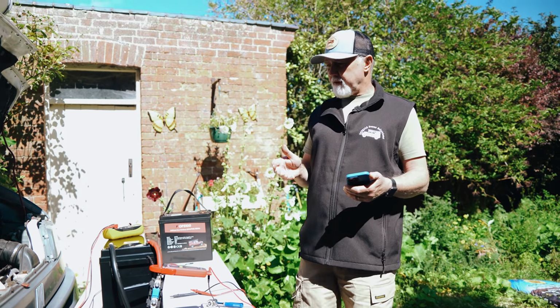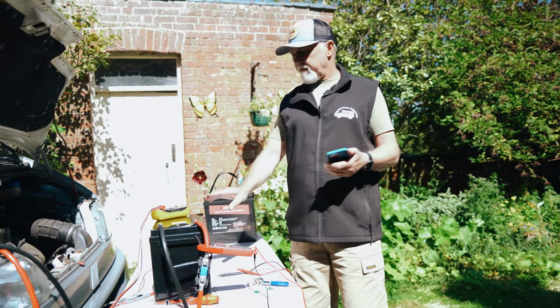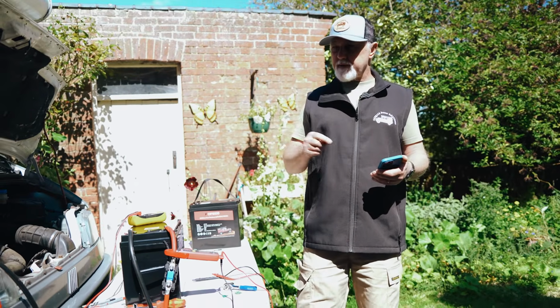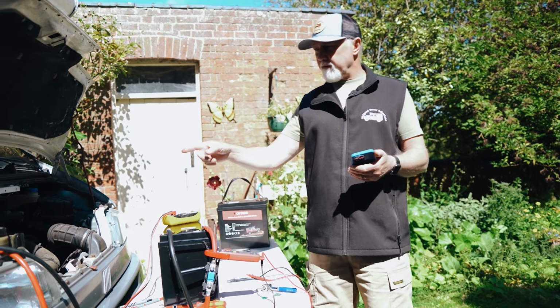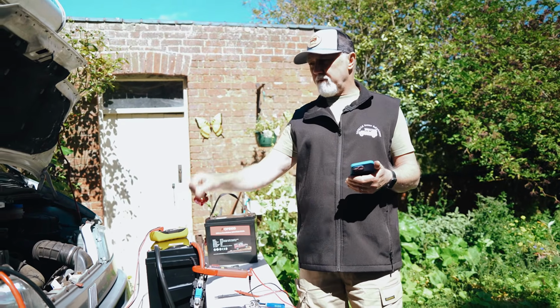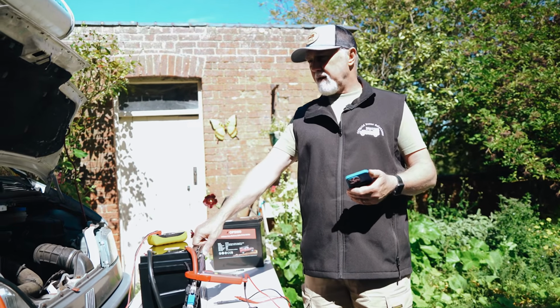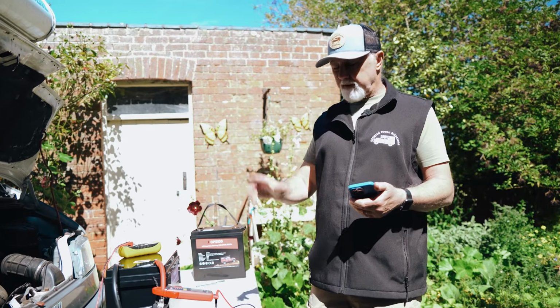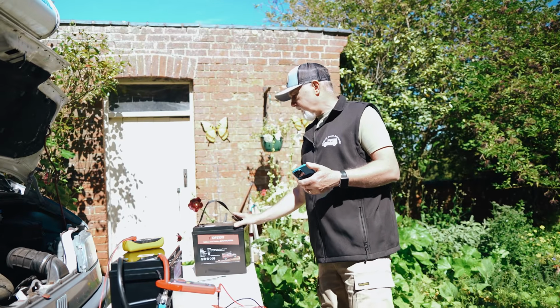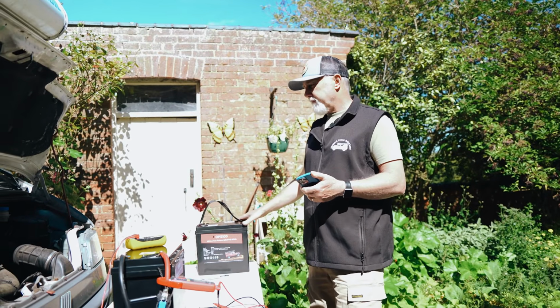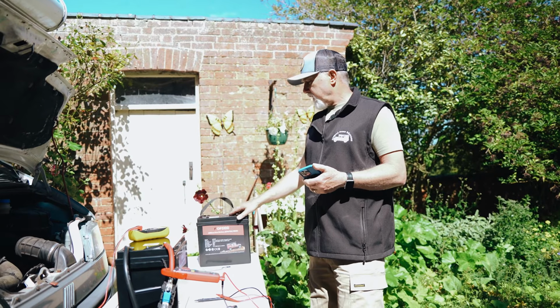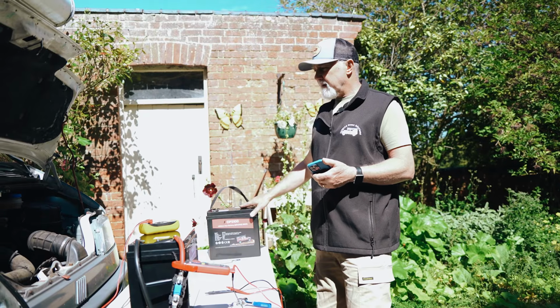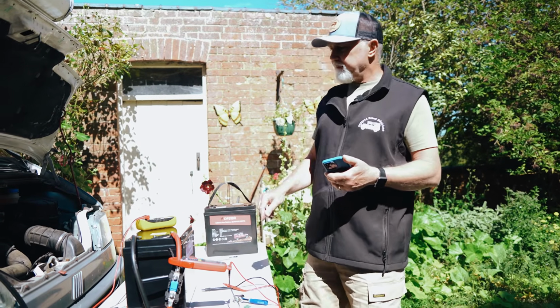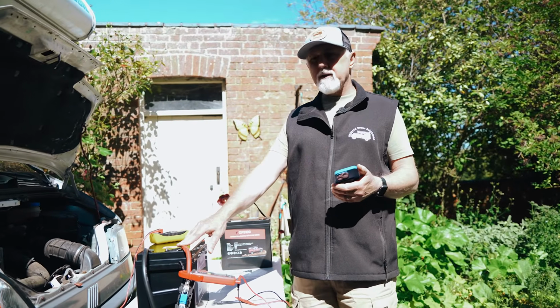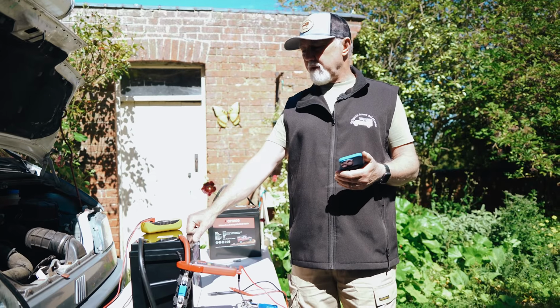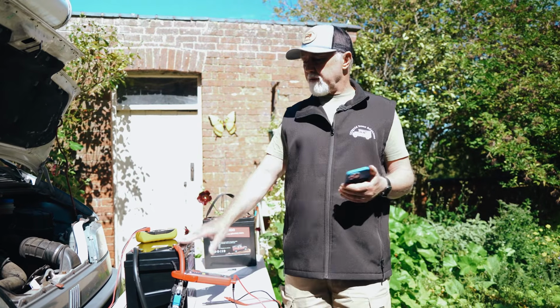Interesting. Right, in conclusion, we've run the test on two different batteries, a 100 amp and a 280 amp, run on my Hilux 2007 model and on this Fiat Ducato motorhome - an old one, a 94 Reg with a new alternator we upgraded to, I think a 160 amp alternator. We blew a few fuses that we replaced, but the smaller battery peaked at 40 and came down quite quickly, so you need to account for the fact that it could draw up to 40 amps even for a short period and fuse it appropriately. This one peaked up to about 70 for a short while, then came down, and for the most part was knocking on about 40 or just under. So overall, around about 30 amps, around about 40 amps.